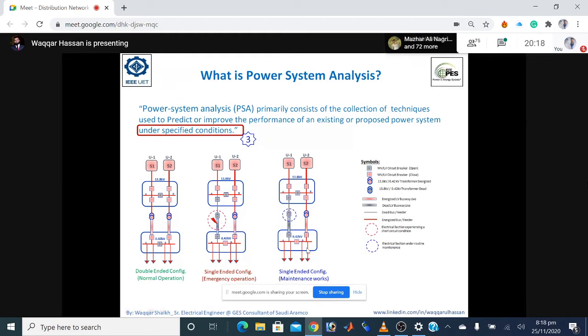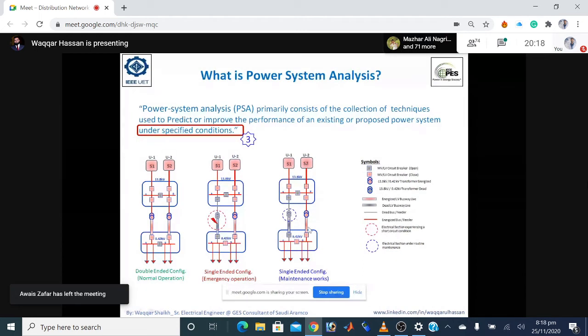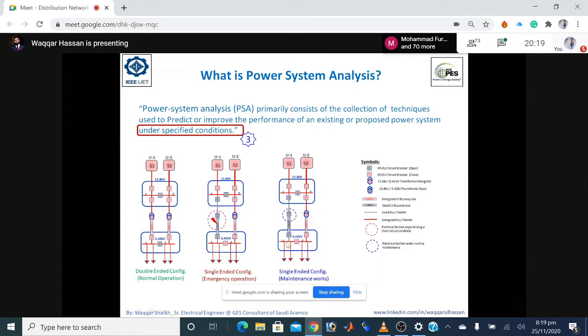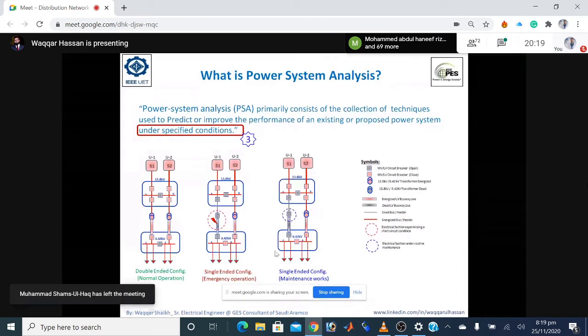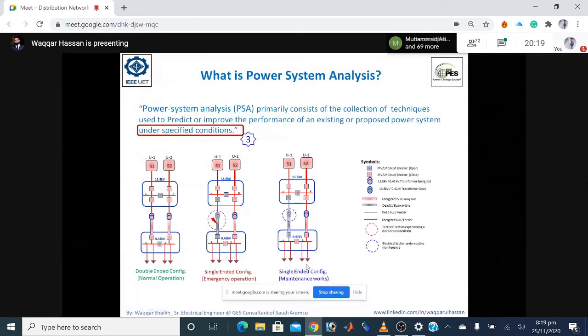Another third example can be seen on the right side. Here there is no outage, but we want to do preventive maintenance on the transformer, so we switch off this part of the network. When we do this, we would close the bus coupler to keep continuity of service to the entire distribution network. So we intentionally switch off this network, making the single transformer take the load of the entire installation - another type of single-ended operational configuration related to maintenance works.